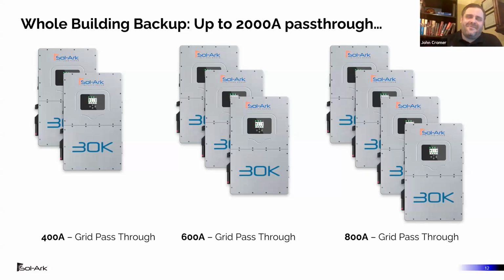For the advanced students in the audience, this grid pass-through capability means that the grid relays within Sol-Ark inverters are oversized compared to our competition. And what that allows us to do is multiple inverter installations where you get 10 inverters operating in parallel when you switch and do that seamless transfer from grid tied mode to backup mode. That grid relay is a failure point, and the smaller the grid relay, the higher the risk. So even when you're doing multiple Sol-Ark inverters in parallel, knowing that we have that oversized grid relay should give you the confidence to know that we can do seamless transfer with parallel inverters in a reliable manner.